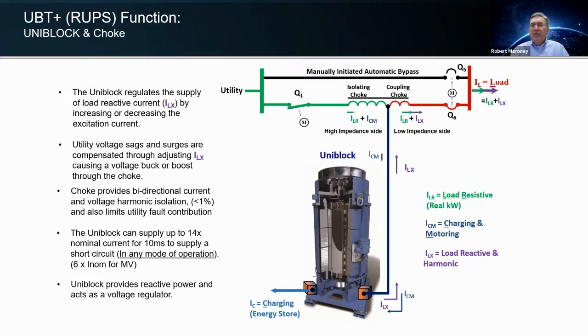So now we've started to build this UPS. We've got your utility connection, your choke with Q1, and Q6 gives you that output isolation per code. Q5 is to be initiated in a manually initiated automatic bypass system in the failure mode. You'll also notice that there's no static bypass in this system.